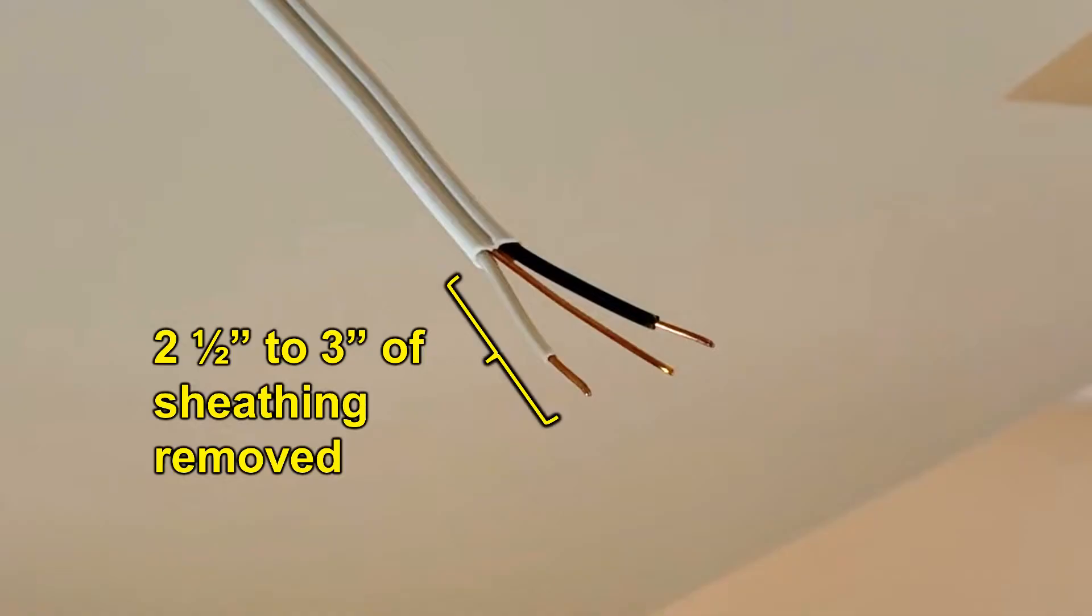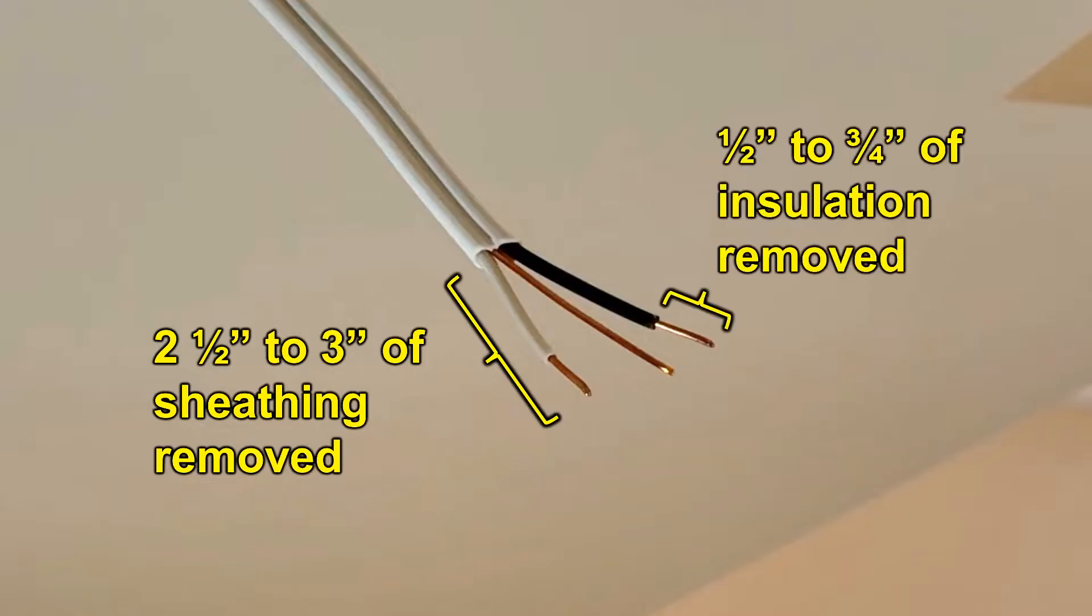Now after you run the wire you should cut about two and a half to three inches of sheathing off of the cable, and each of the black and white wires should have about one half to three quarters of an inch of insulation stripped off. This prepares it so that it's going to be able to go into the housing for the light but not have too much wire in there that it causes a problem trying to fit everything in and close the top again.